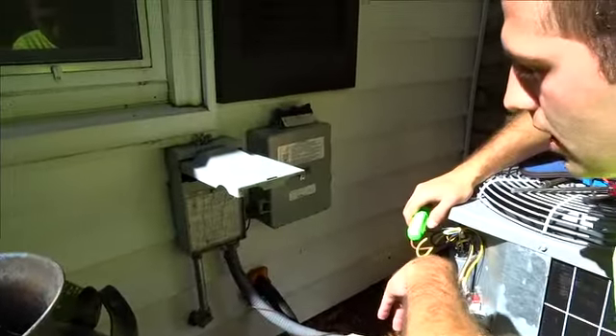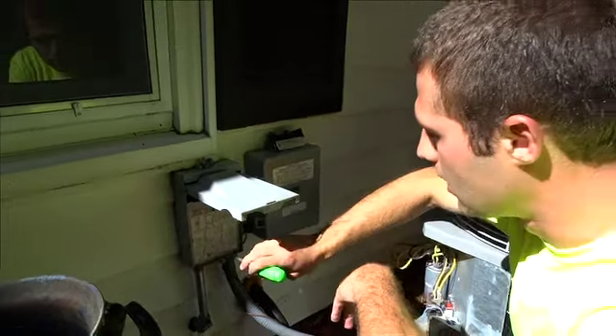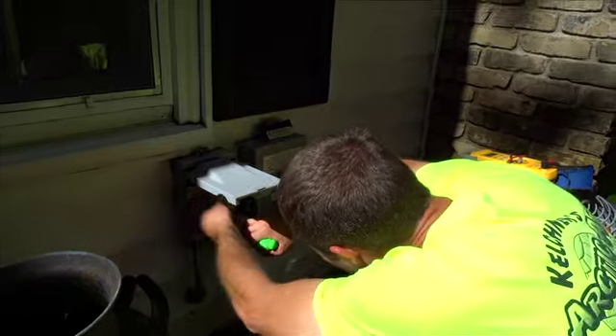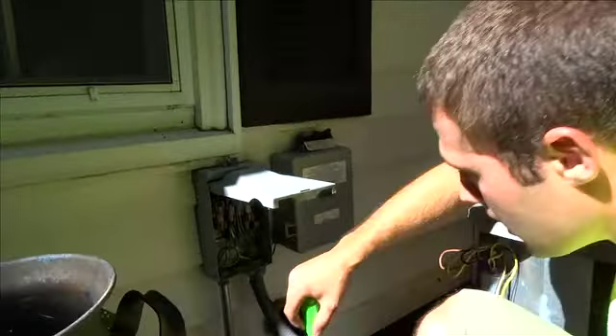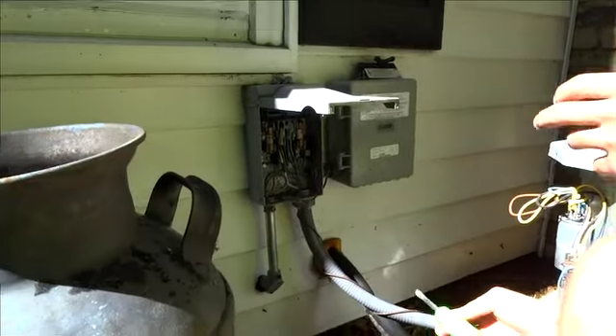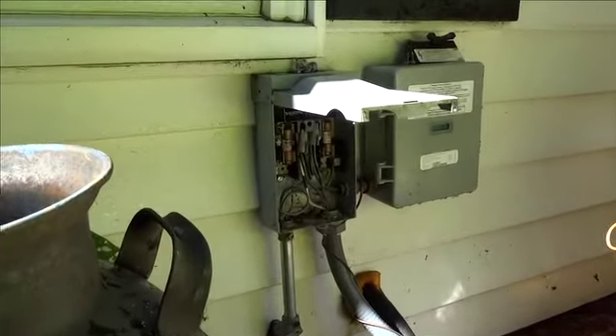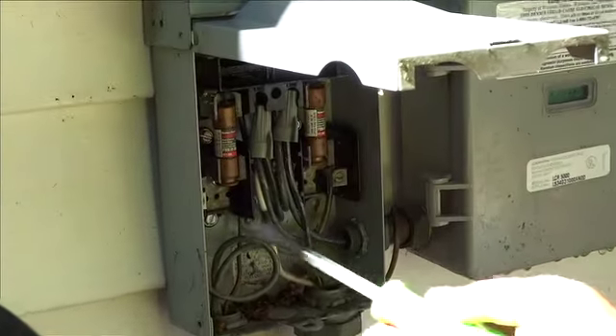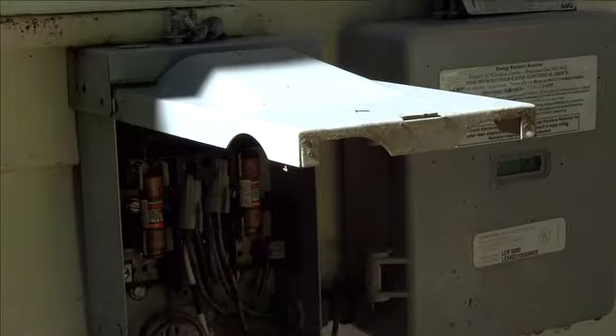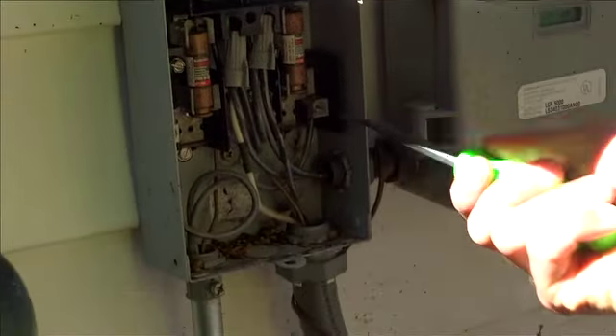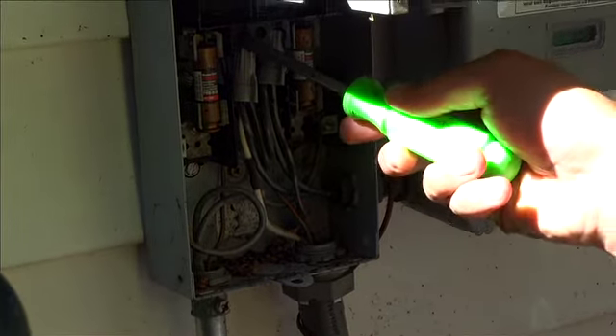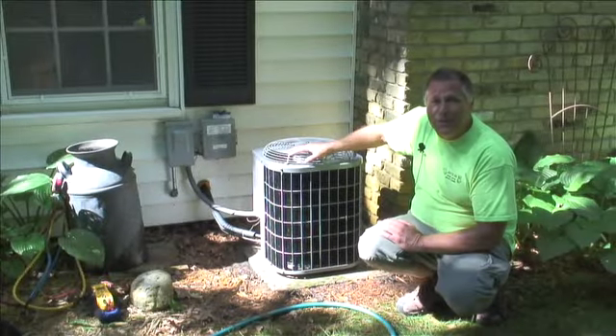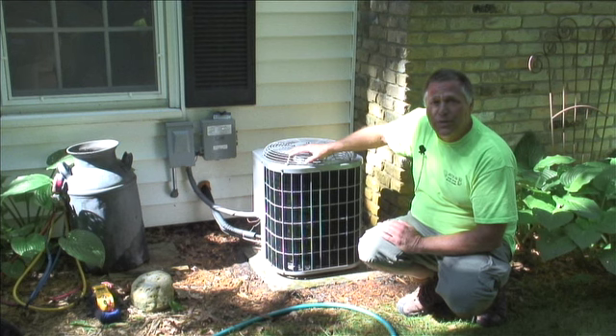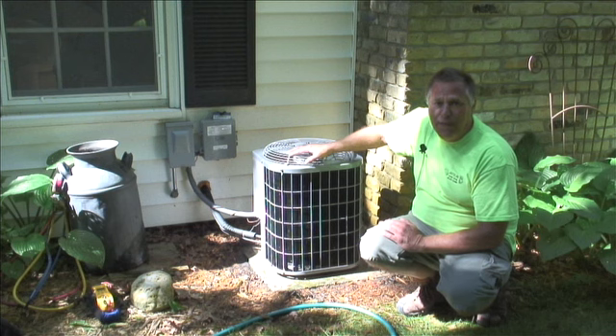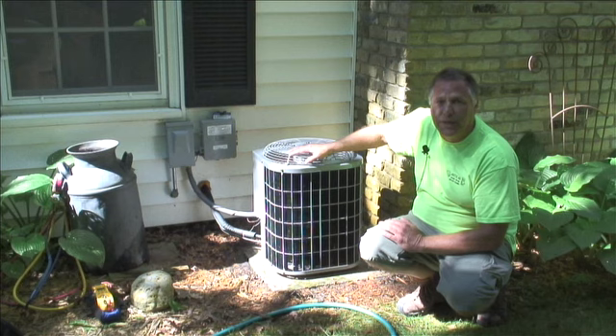Another important thing that we check is all the electrical connections and the high voltage. If you have loose connections in any of the high voltage circuit, it can actually arc and spark and sometimes start a fire. So we always check for proper electrical connections on all the high voltage circuits. Make sure they're tight. The next step of the process is checking the inside A coil to make sure it's clean and properly draining, and also checking the drain lines and the filter in the furnace to make sure everything is clean and clear.